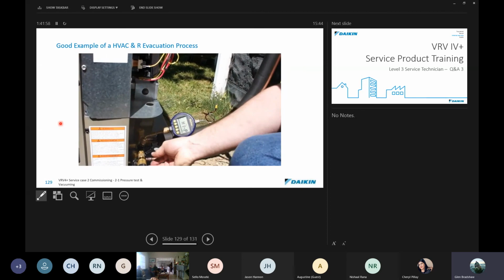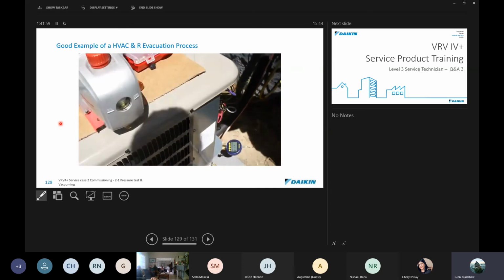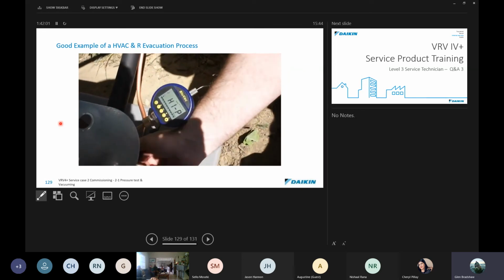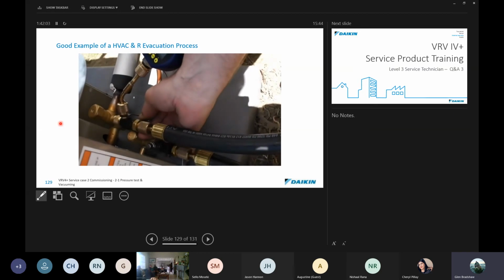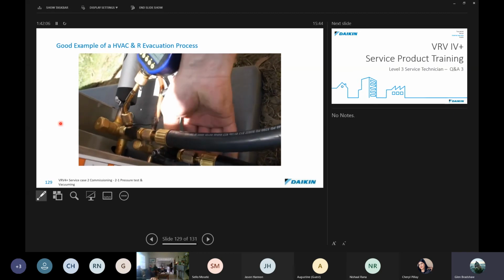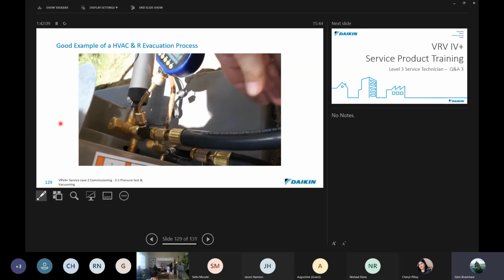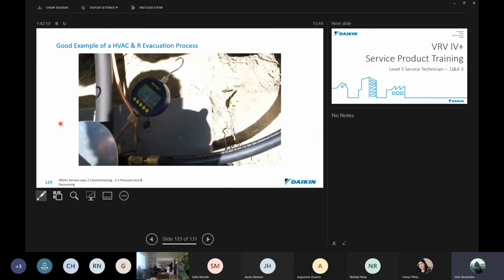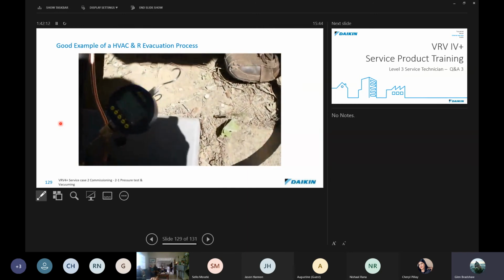Alright. Vacuum pump. And I'm going to slowly crack this valve here and let it handle that pressure. Alright. And now we're good to go. So that'll start reading at about 20,000 microns.